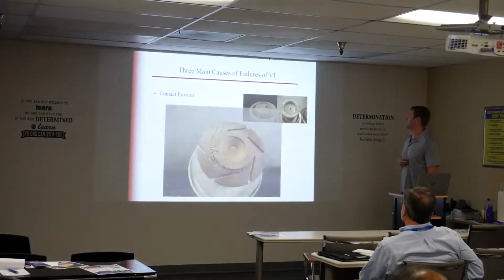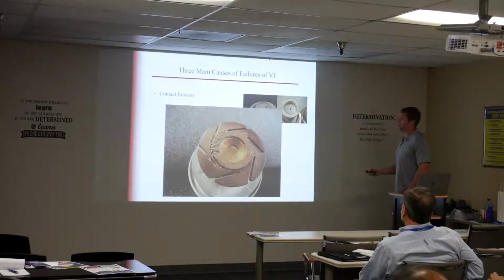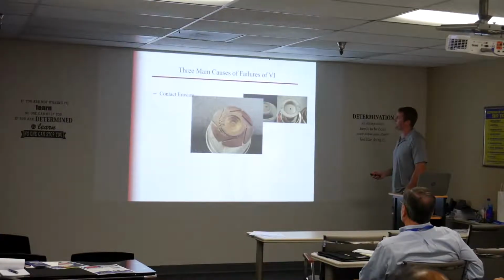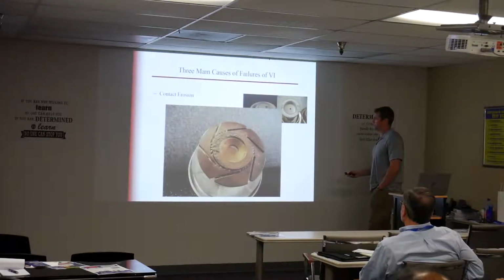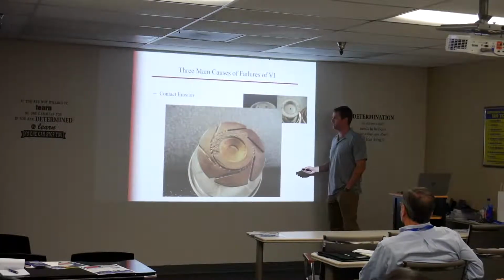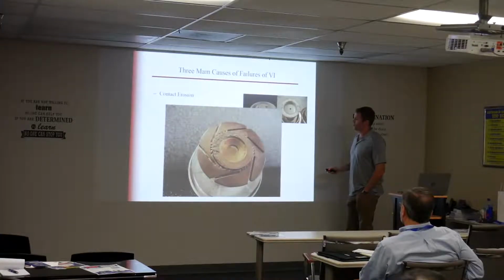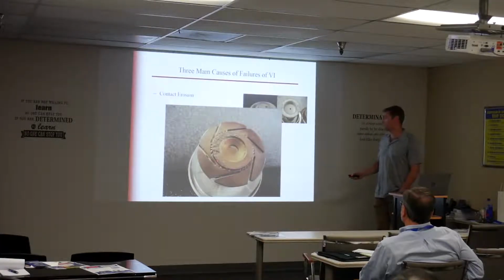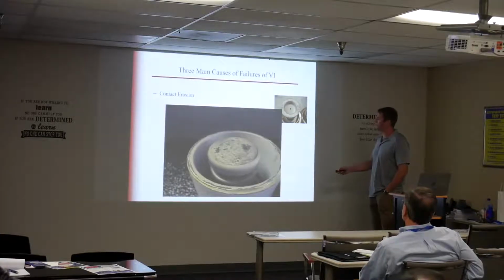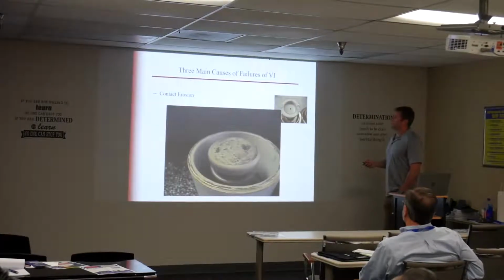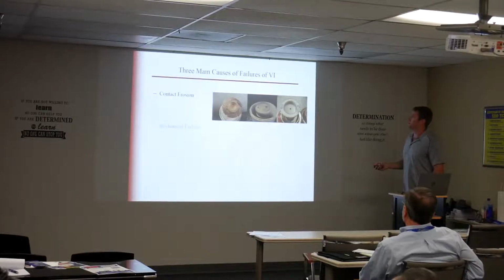So here's just a couple of pictures where we've taken these bottles and opened them up and show examples of contact erosion. That's actually why the inside interrupter has this geometric design, because whenever you do draw an arc, you want the arc to move and not just sit in one spot and burn a hole or weld a hole in the contacts. So this geometric pattern produces a field that tries to keep the arc moving or kind of dancing around instead of sitting. This is the other design, a butt contact. So contact erosion is the number 1 main cause of failure of vacuum interrupters.